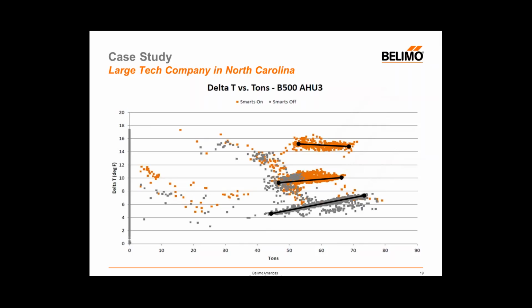And each one of the data sets represents a different way the energy valve was controlled. So this was from a single energy valve that was on a single air handler. Nothing physically was changed from any of this data. All that was changed was the control strategy that controlled the energy valve.